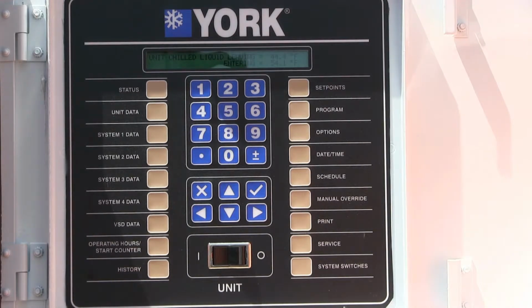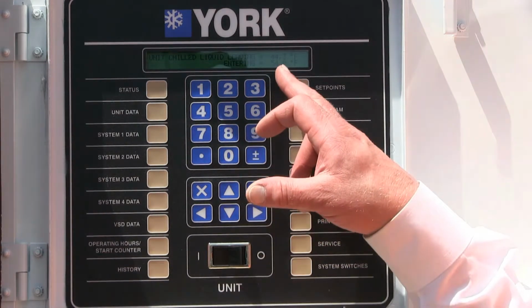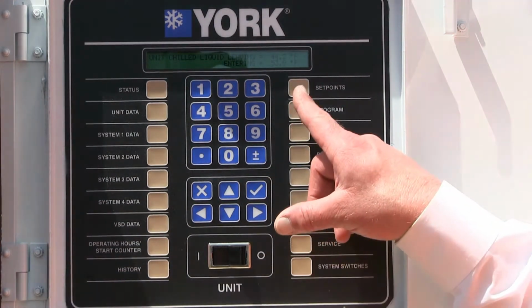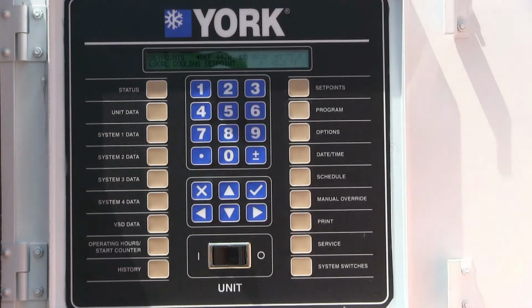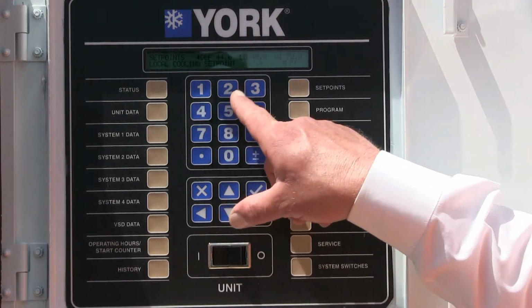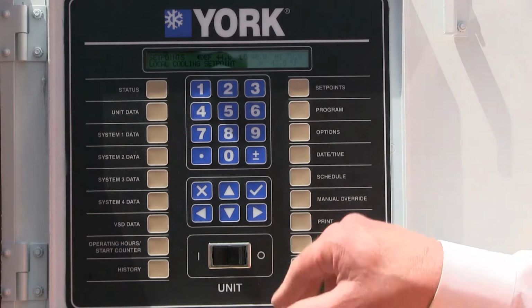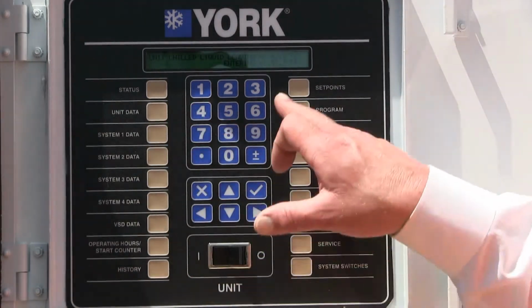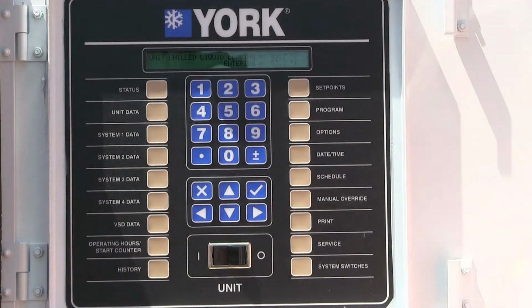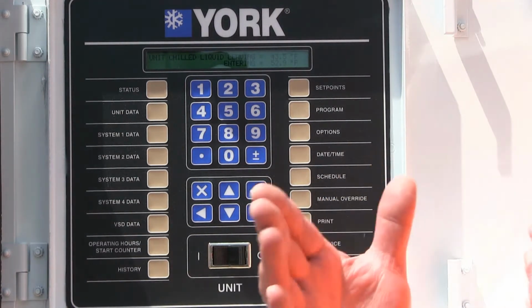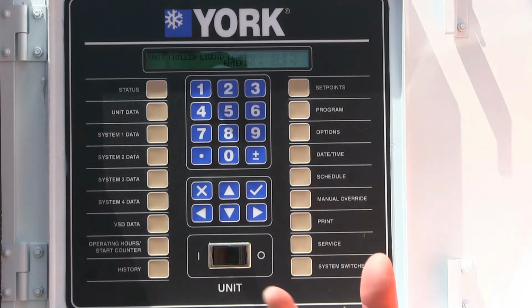Okay, the machine's been running for about 10 minutes. You notice now we've got our set point, I raised it up, we've got it at 45 degrees. I'm going to lower that down to 43 degrees, enter, and we'll go back to unit data, and we've got 43 degree leaving, 53 degree return, 10 degree split between the entering and outlet of the chiller at full load, which is pretty traditional for the design. And the chiller's got the water down, so now it's time to turn the air handlers on.